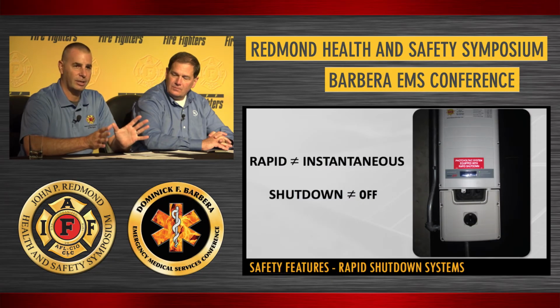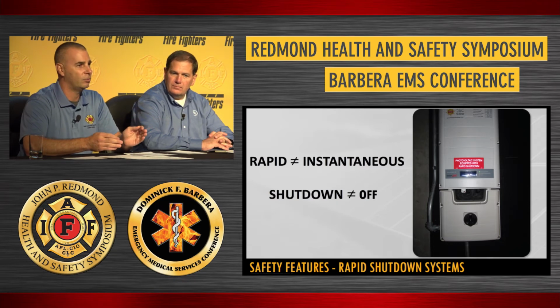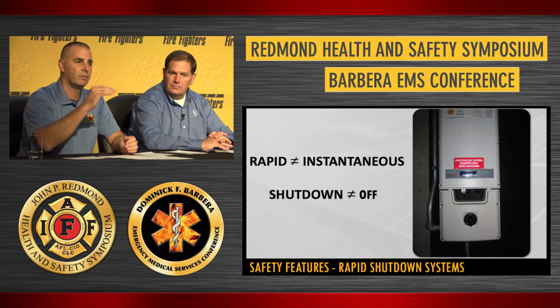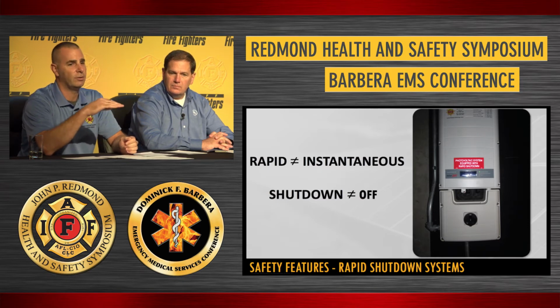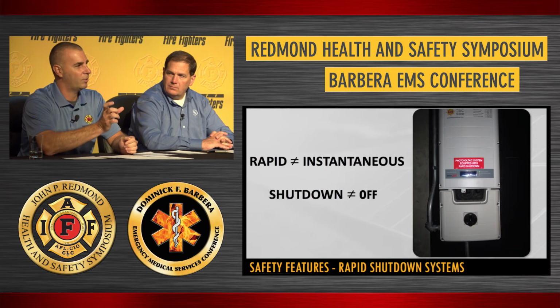They added into the code in 2014 a term called rapid shutdown. In the fire service, we think rapid means fast and shutdown means going to a zero state. With rapid shutdown, that's not necessarily the case. It's rapid, but the rapid being 30 seconds, and shutdown is to a limited state - 30 volts DC within 30 seconds. That's what the code states rapid shutdown is, 30 volts being that touch-safe level.